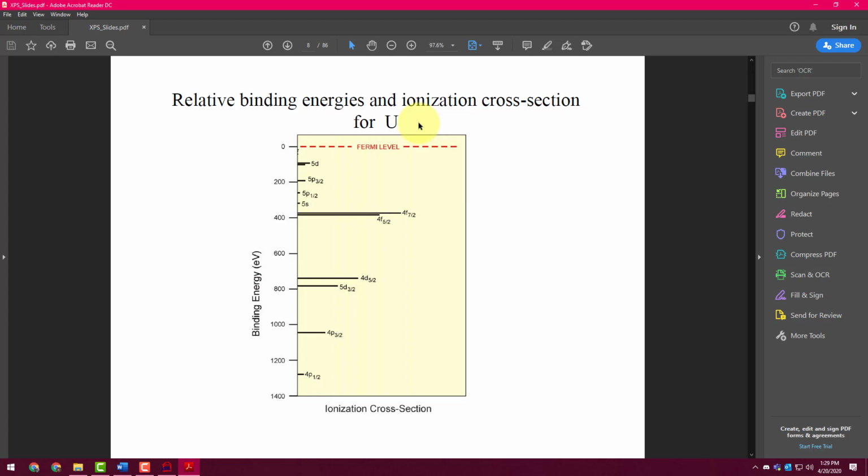So just because you have equal amounts of two elements in a sample does not mean that they are going to ionize the same amount. The same number of electrons are not going to be ejected by the X-rays. But luckily for us, that's a pretty standard event, and it was easily calculated by physicists in the past who developed this technique. And so there's actually a giant table, commonly called a Scofield table, that is full of these correction values that we can use to make sure that we get accurate concentrations.